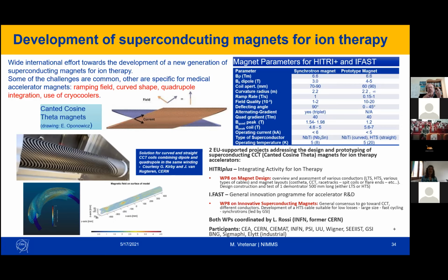Each of them is a solenoid that produces a magnetic field with a certain angle. You see here two angles, but if you combine them, it gives the vertical magnetic field that you want in a superconducting magnet.